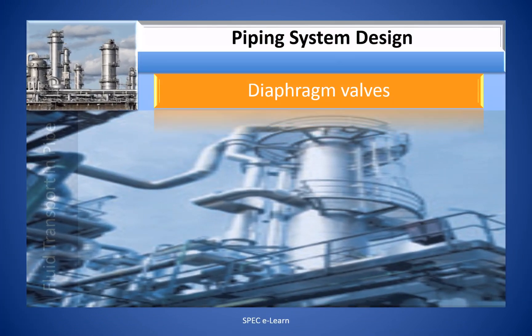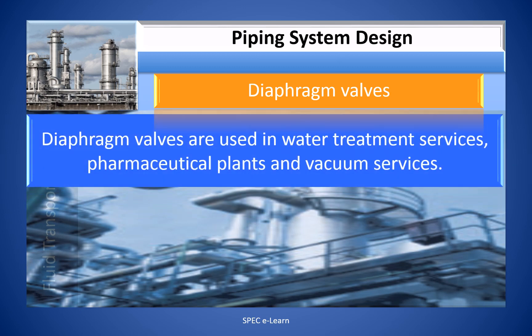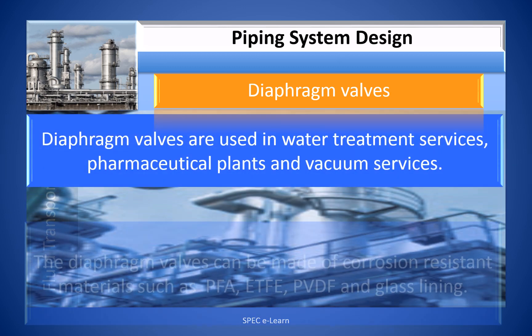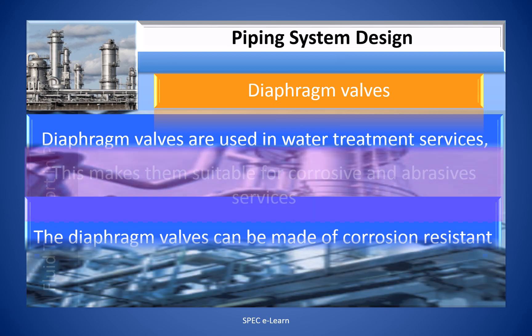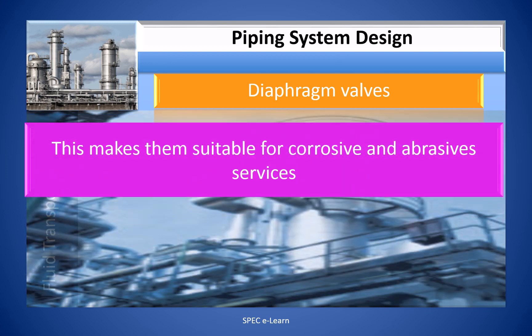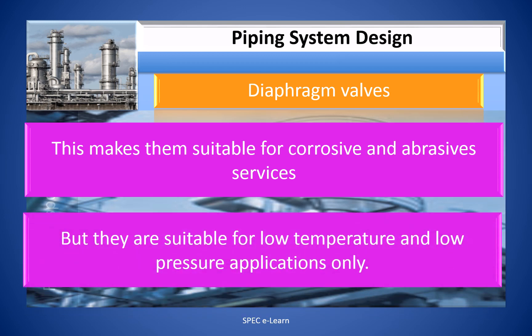Diaphragm valves are used in water treatment services, pharmaceutical plants, and vacuum services. They can be made of corrosion-resistant materials such as PFA, ETFE, PVDF, and glass lining, making them suitable for corrosive and abrasive services. However, they are suitable for low temperature and low pressure applications only.